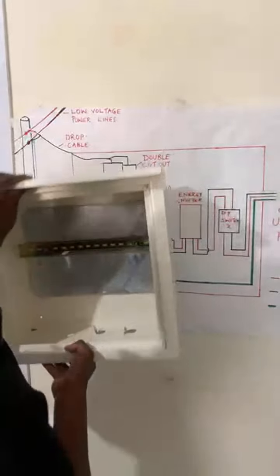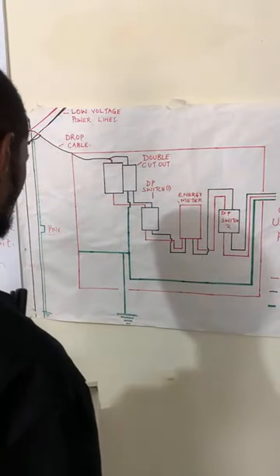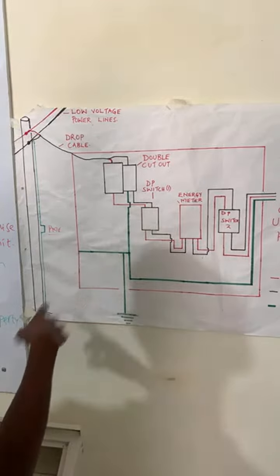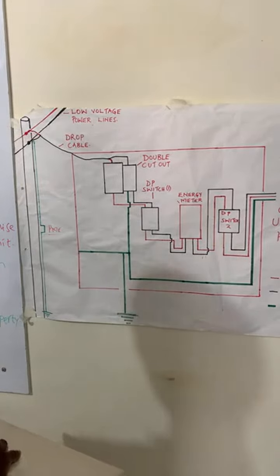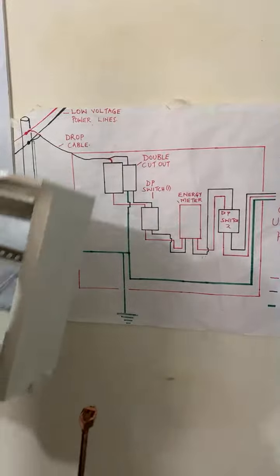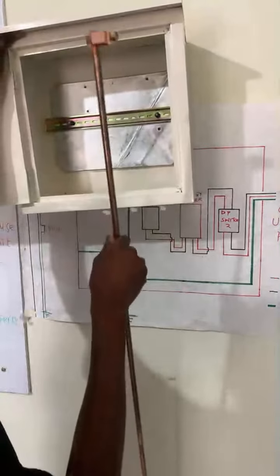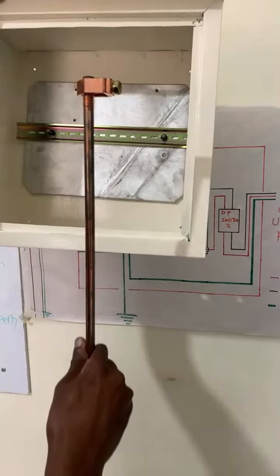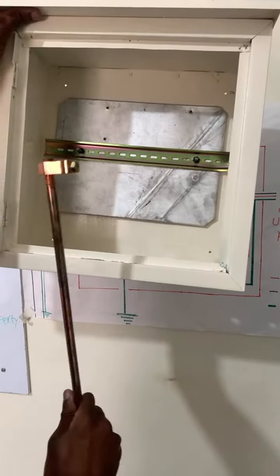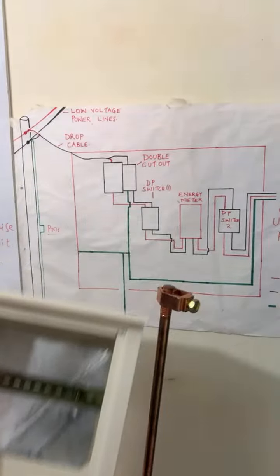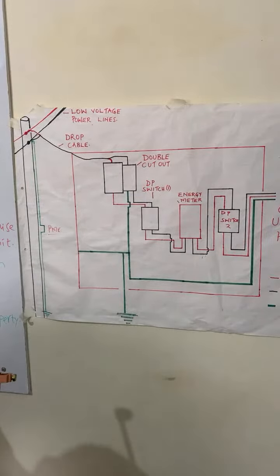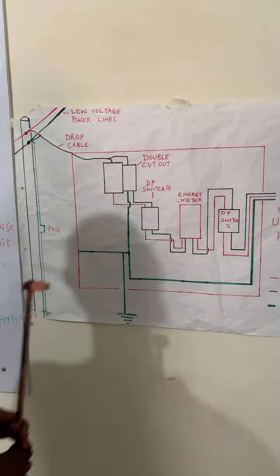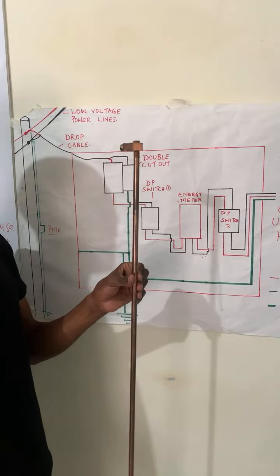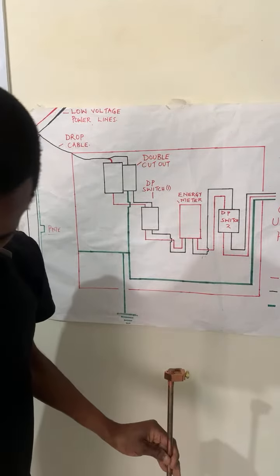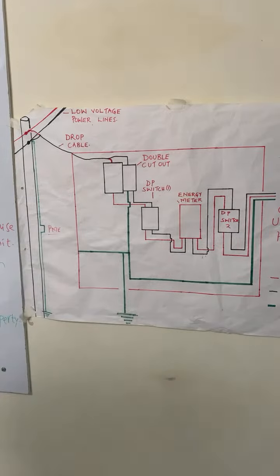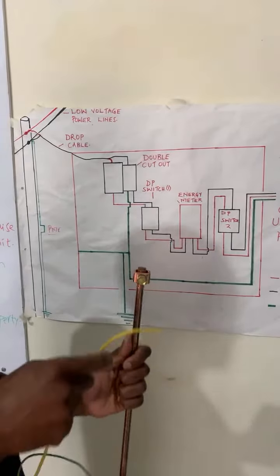Now at the meter box, we have said that there is this connection at this point. So from the meter box now, it will go all the way to the earth rod. So basically you have the meter box, you have the earth rod, which is this one here, so that they have to be connected together. They have to be bonded. All right. So this is our earth rod. All right. And then we have our earth cable here.